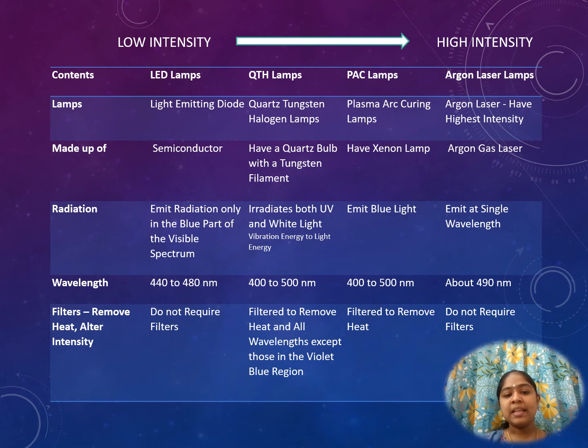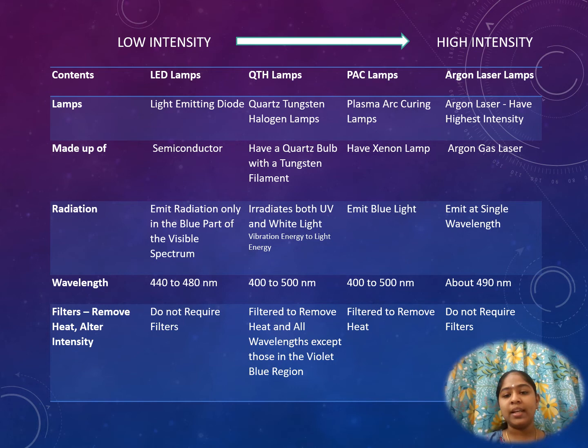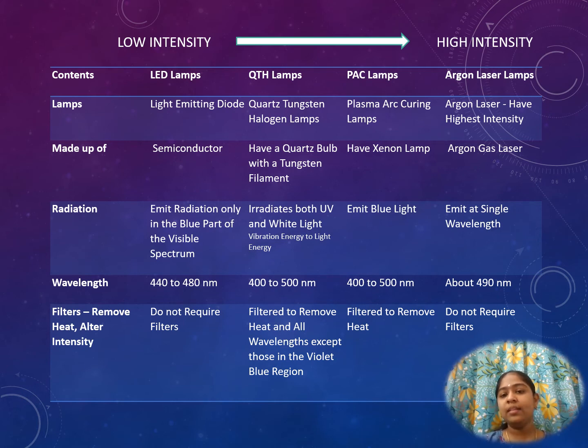Regarding radiation: LEDs emit radiation only in the blue part of the visible spectrum. QTH irradiates both UV and white light, involving conversion of vibrational energy to light energy. PAC lamps emit blue light only. Argon laser lamps emit at a single wavelength of 490 nanometers. Wavelength ranges: 440 to 480 nanometers for LEDs; 400 to 500 nanometers for QTH; 400 to 500 nanometers for PAC; and about 490 nanometers, a single wavelength, for argon laser.